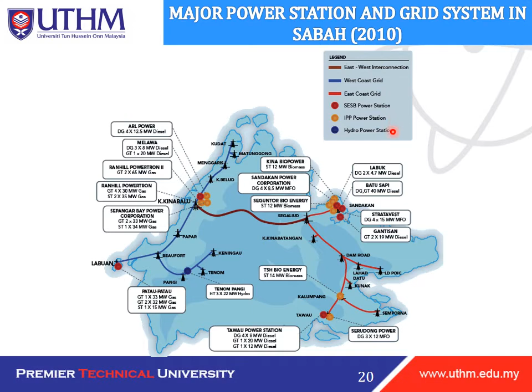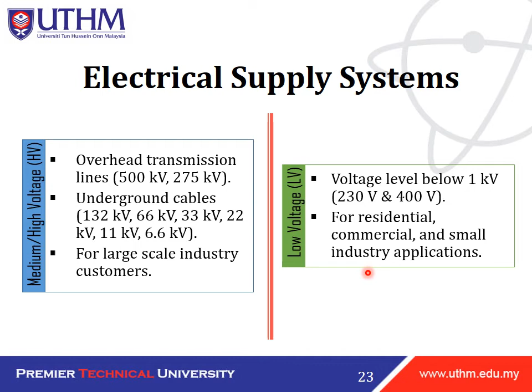So now we go to the third subtopic, which is electric supply system. The electrical supply system can be divided into two: medium or high voltage, in short HV, and low voltage, in short LV. So, medium or high voltage is used for overhead transmission lines such as 500 kV and 275 kV. And then for underground cables, the voltage ratings are 132 kV, 66, 33, 22, 11, and also 6.6 kV. High voltage is also used for large scale industry customers. And then low voltage is used for voltage levels below 1 kilovolt, such as 230 volt and 400 volt. Low voltage is also used for residential, commercial, and small industry applications.